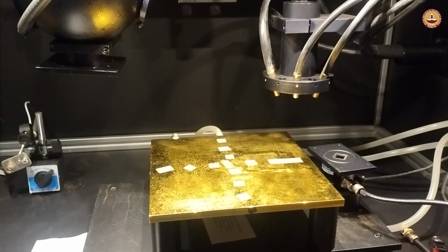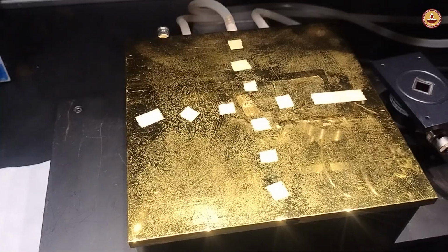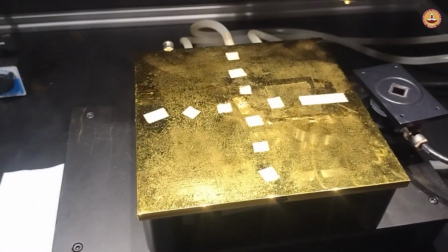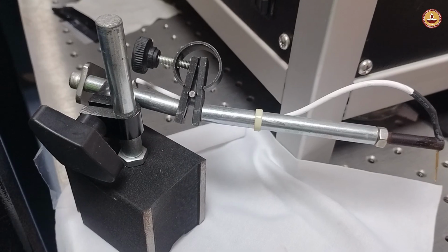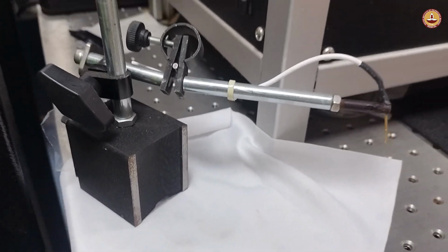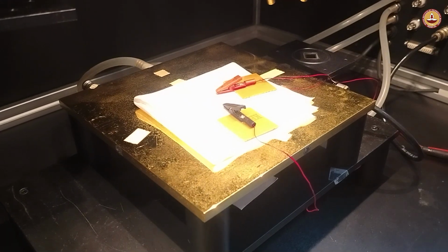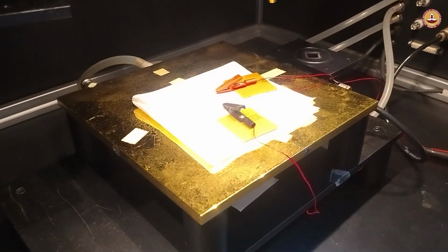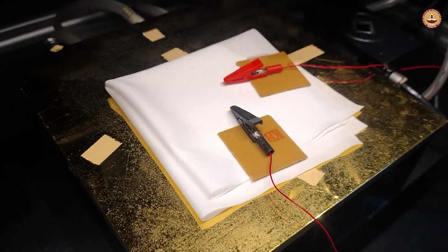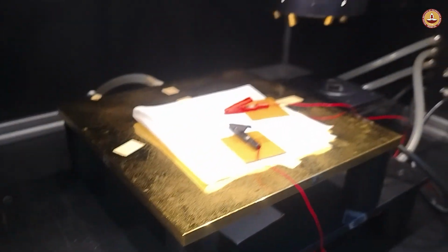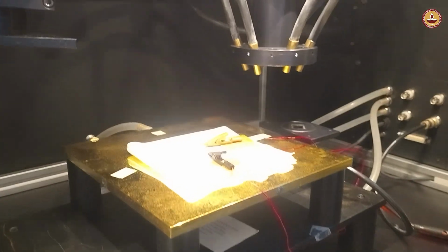This is the sample stage of the EQE measurement system. The conductive stage is designed to mount bottom contact devices, particularly those with top illumination configuration, along with manipulators for precise contacts. Crocodile clips of this type are used for third generation solar cells that require illumination from the bottom side, allowing for flexible and reliable electrical contacts during measurements.